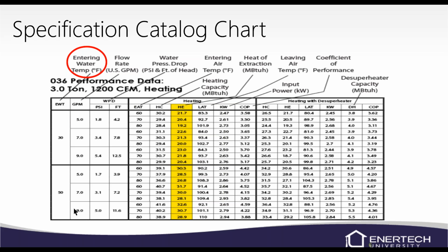So normally in our manuals, we're pretty good, especially now going forward. In this chart, we see a 30, a 50, probably a 70 and a 90. And that's kind of a big temperature difference. So if you had 40-degree water, you'd have to kind of interpolate this chart. So we have broken it down. I think now we have 25-degree, 30-degree, and then we go to 10-degree increments. So 40, 50, 60. So we can get a little bit closer to where you're at.